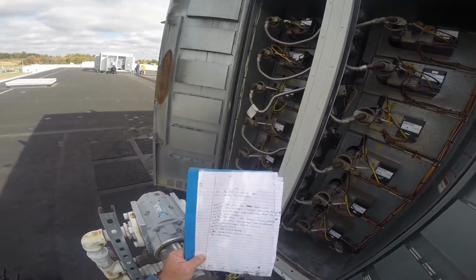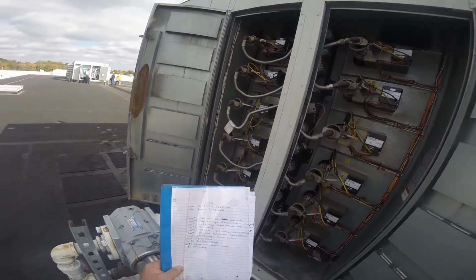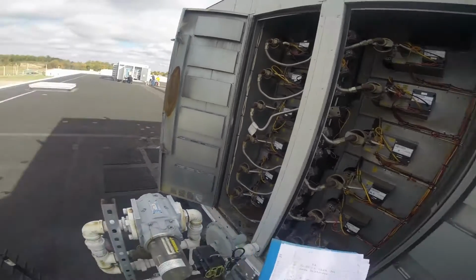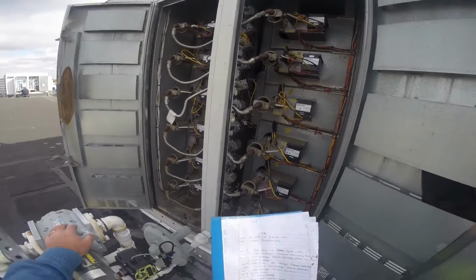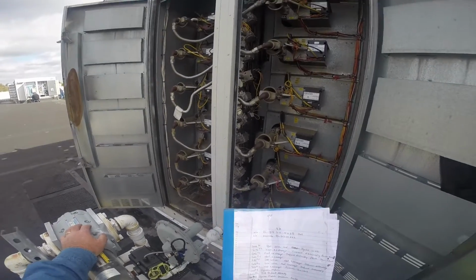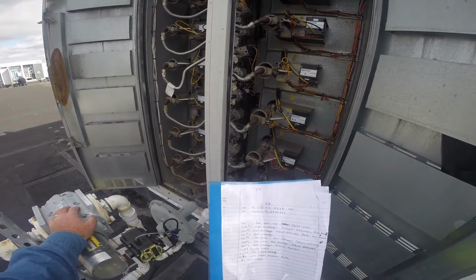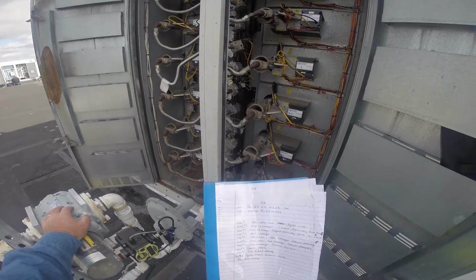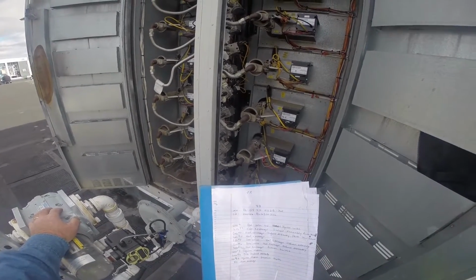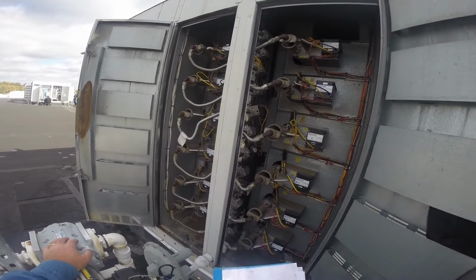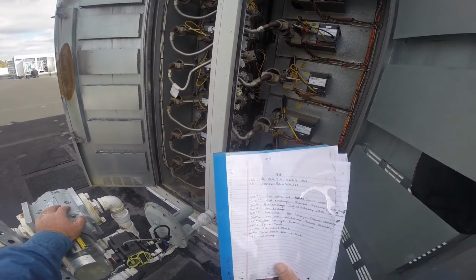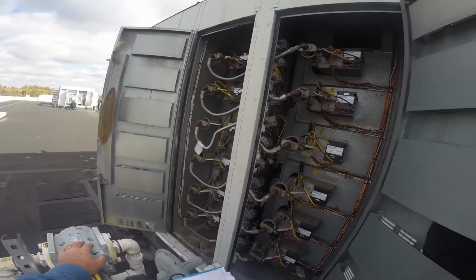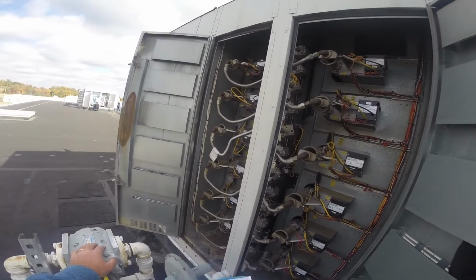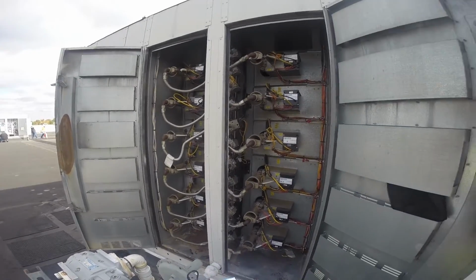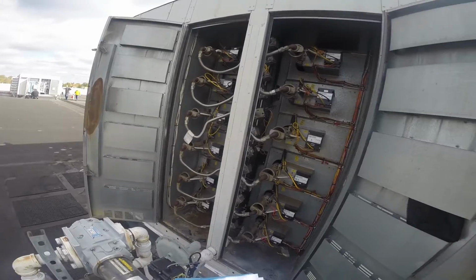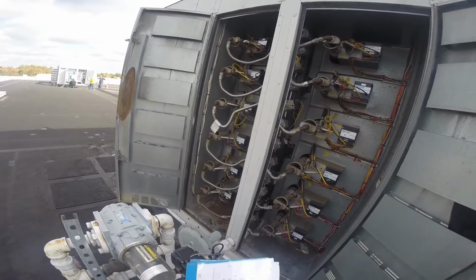Heat exchanger's bad. Number 5, gas valve's bad. Heat exchanger's not pulling with the proper vacuum. It's got to have some kind of seal or crack in it. Number 6, gas valve, heat exchanger, inducer draft motor. Number 7, heat exchanger, pressure switches are not operating properly. Number 9, we know it's got a bad induced draft motor, so we couldn't really test it because we didn't have a good motor on it to pull a vacuum. We were assuming that with the corrosion and stuff, it's probably not in good shape either.